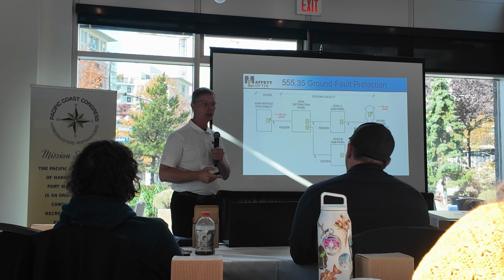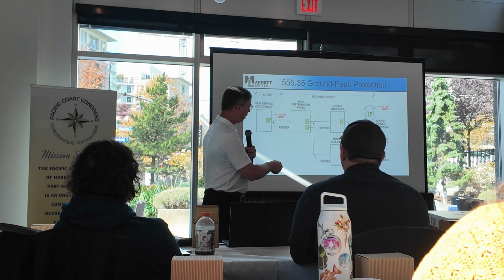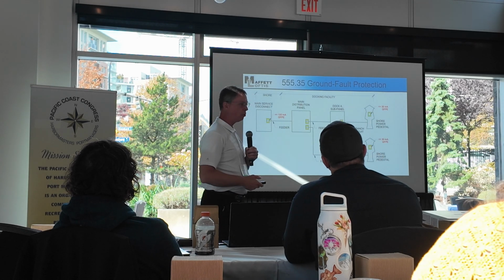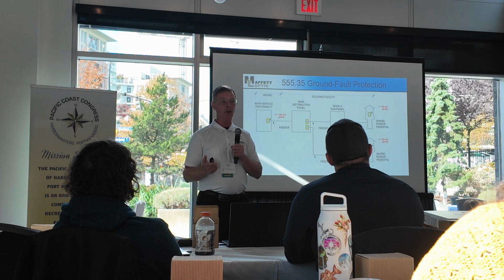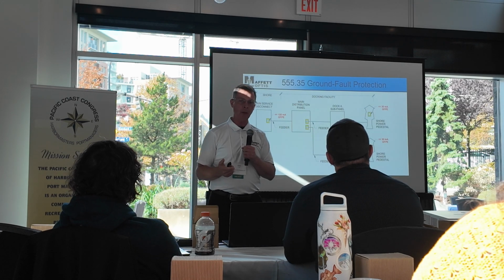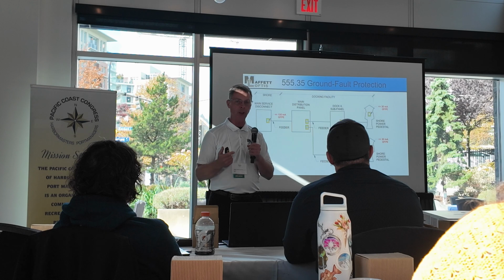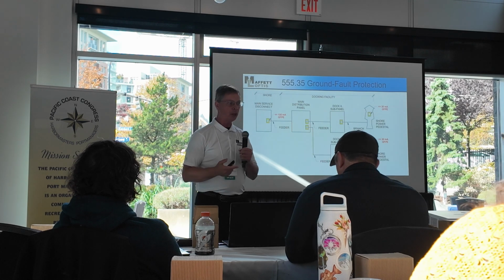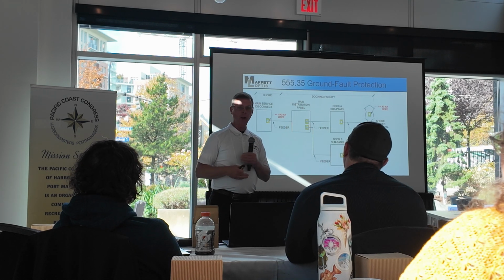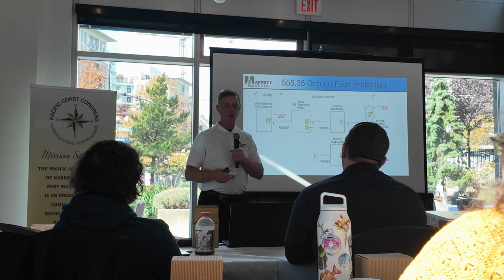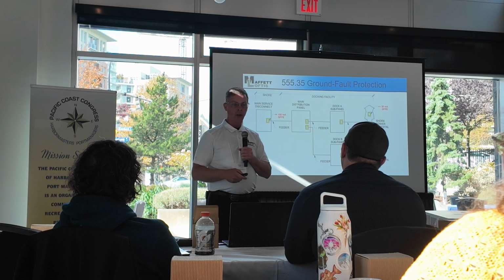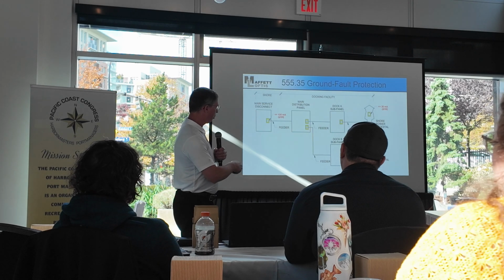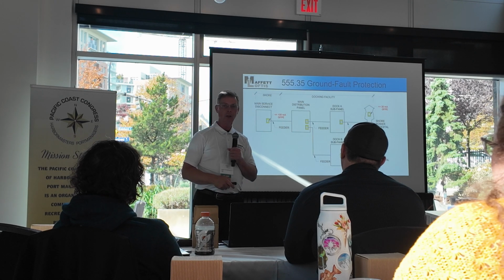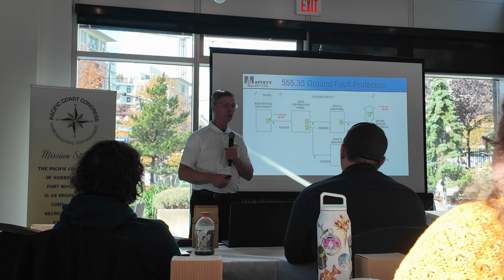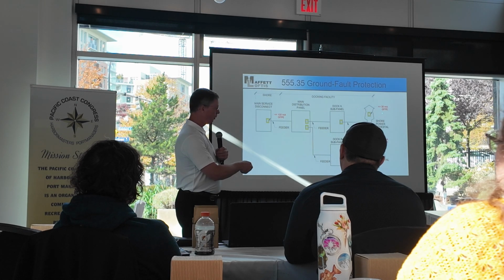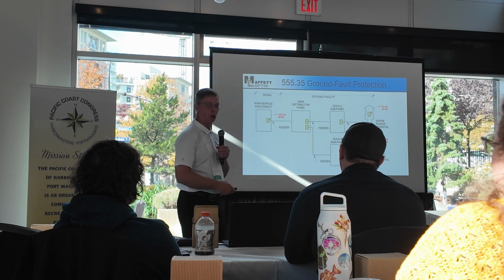But what if you have a boat that comes in and you plug into that shore power, and that boat, I've seen water heaters, for example, pull 7,000 milliamps of leakage current because it had a crack in the element and it was leaking into the water system. So say that the thermostat in the water heater kicks in and it leaks, just say, 400 milliamps. Okay, what will trip? The 30 milliamp trip or the 100 milliamp trip? If that boat instantaneously starts leaking 400 milliamps, is that 400 milliamps greater than that? Absolutely. Is it greater than that? Absolutely. So what's going to trip?